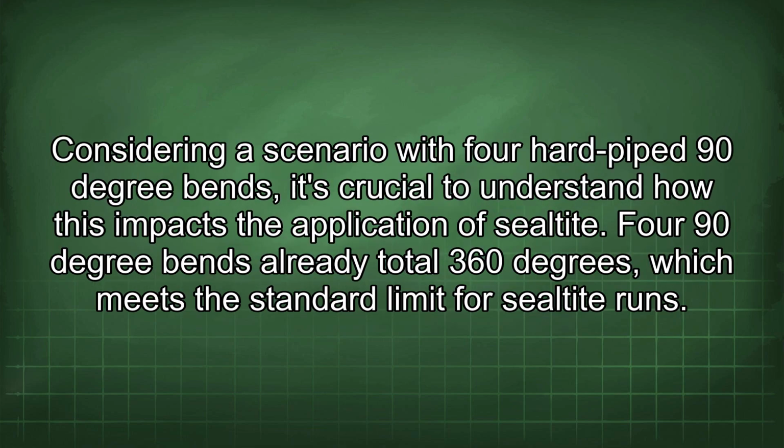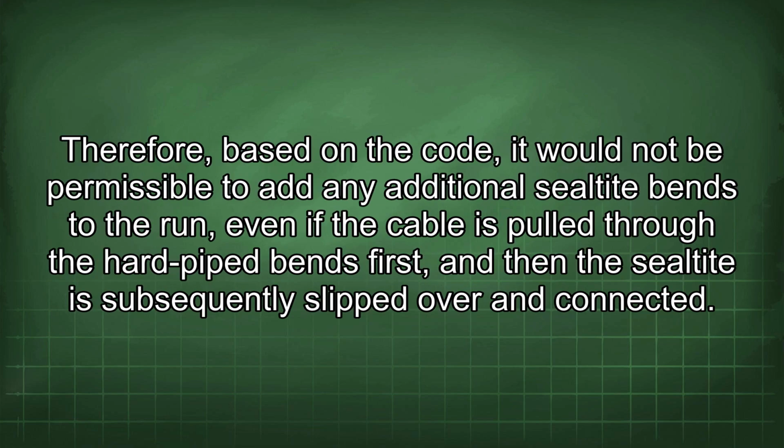Considering a scenario with 4 hard-piped 90-degree bends, it's crucial to understand how this impacts the application of Sealtite. 4 90-degree bends already total 360 degrees, which meets the standard limit for Sealtite runs.